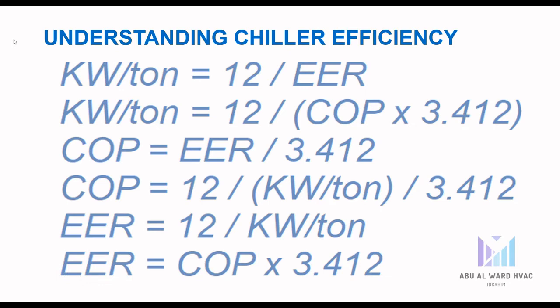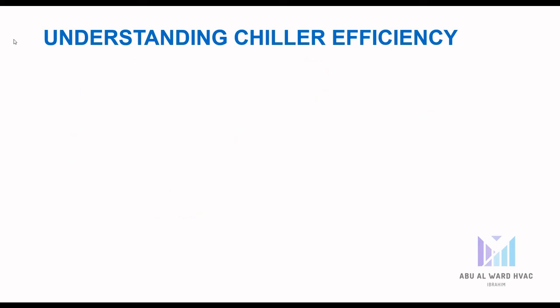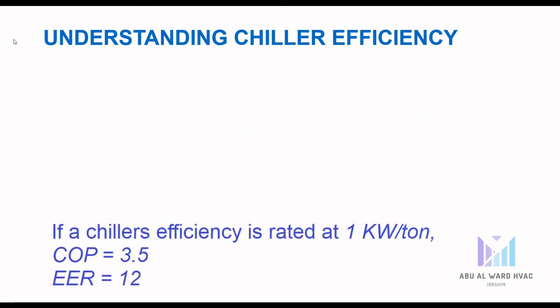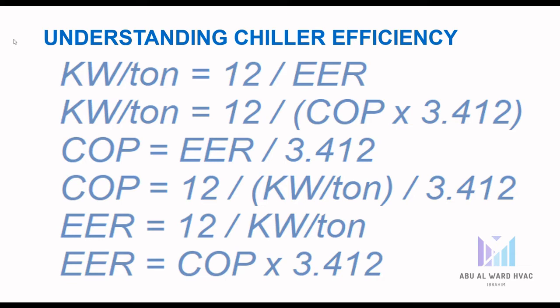Understanding chiller efficiency: below are a few simple formulas for converting between various units of energy efficiency for electric motor-driven chillers. All of these formulas can be used to calculate COP, kilowatts per ton, and EER. For example, if a chiller efficiency is rated at 1 kilowatt per ton, substituting into the formulas gives EER equal to 12, and COP equal to 12 divided by 3.412, which equals 3.5.